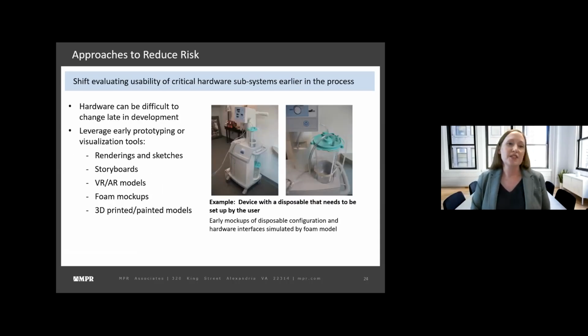Another approach to reduce risk is to think about shifting usability evaluation of critical hardware subsystems earlier in the process. Hardware is extremely difficult to change late in development. If you wait until all the way at the end of development when you've got a functional, fully integrated pre-production prototype, and then you find out the power switch is not in the right spot on the device, and I need to move it where users can recognize and reach it, that could be a major design overhaul that could impact electrical, mechanical, and our EMC testing. So it's really important to get the usability input on any hardware subsystems early in the process.